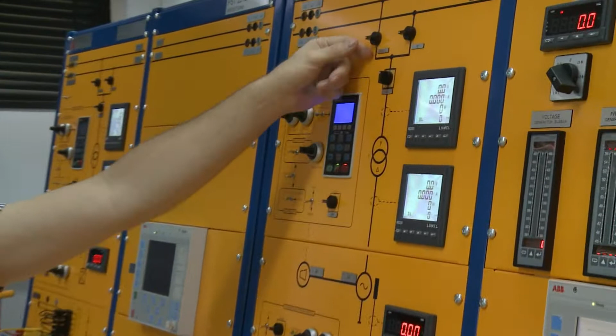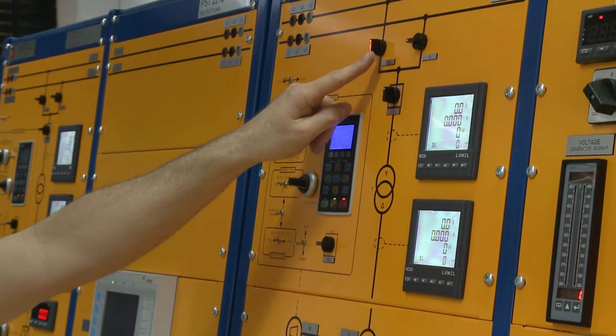If we do it in the opposite order, first we put power through here and then we try to make a connection with this one, it will say no, we can't do it. Behind this switch we have a contactor, so when we close the switch we send a signal to the PLC, and the PLC checks to see if it's okay to close the contactor. If it's not okay, the contactor stays open and the light comes on.